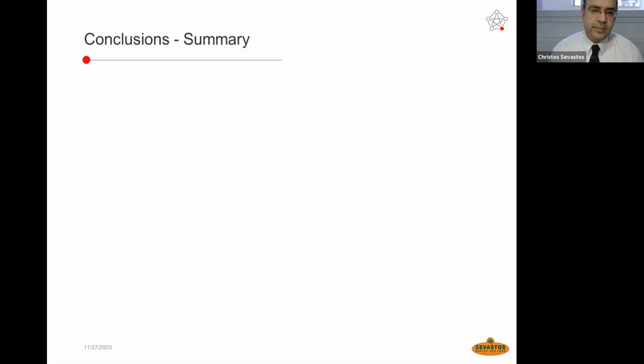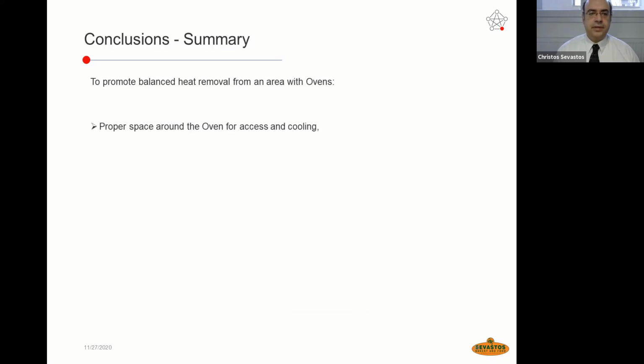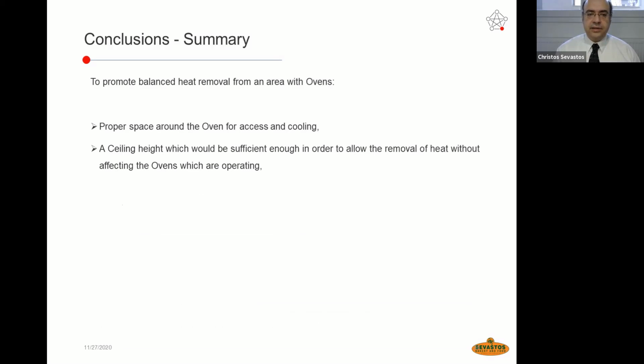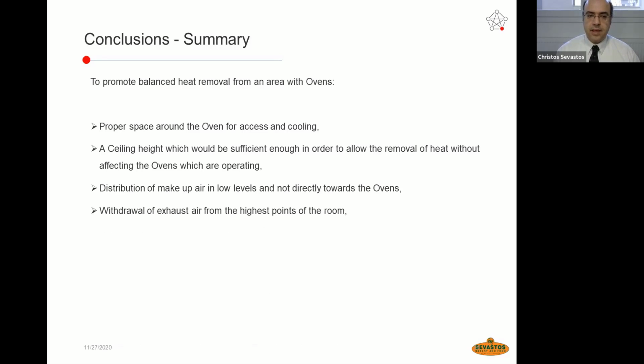Let's go to the conclusions of the presentation. Let's go to the summary. To promote balanced heat removal from an area with ovens, first of all, we need to define the proper space around the oven for access and cooling. A ceiling height which would be sufficient in order to allow the removal of heat without affecting the ovens which are operating. So we need to define the ceiling height. Distribution of makeup air at low levels and not directly towards the ovens, as we have discussed regarding the positive pressurized air ventilation system. Withdrawal of exhaust air from the highest points of the room with powered or non-powered extraction fans.